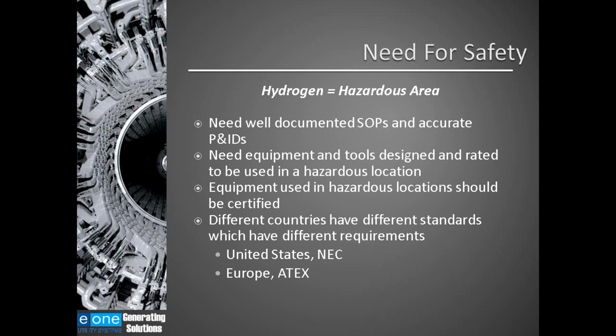Because of the conditions listed, it is very important that safe practices are documented and followed. Hydrogen equals hazard. You need well-documented standard operating procedures and accurate P&IDs — piping and instrumentation drawings. You need equipment and tools designed and rated to be used in hazardous locations, and equipment used in hazardous locations should be certified for that type of location. Different countries have different standards: the United States follows the National Electrical Code; in Europe they follow ATEX or IEC-EX; and countries such as Russia and South Korea have different standards.